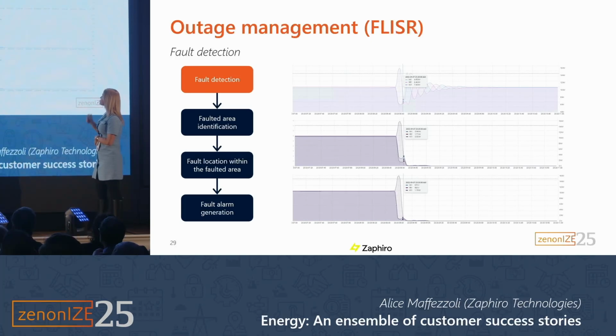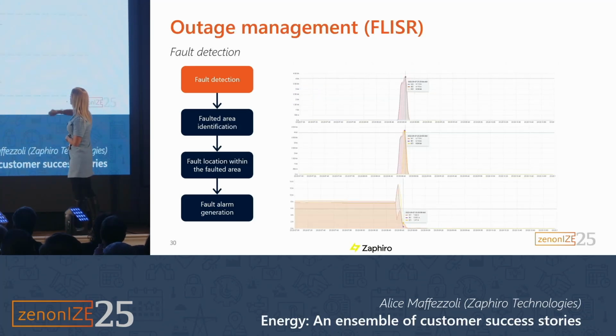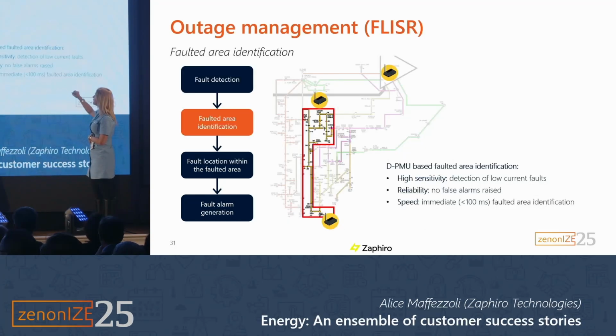So this is what happens. I will show you exactly all the steps. I will show you slowly, but in reality, everything happens in a matter of seconds. So first of all, we have the fault detection. This is what happens in terms of voltage and current. And here you can see the quality of data, so how fast we can detect the measurement and the status. Then we have the faulted area identification, which means that we identify between which PMUs the fault is.